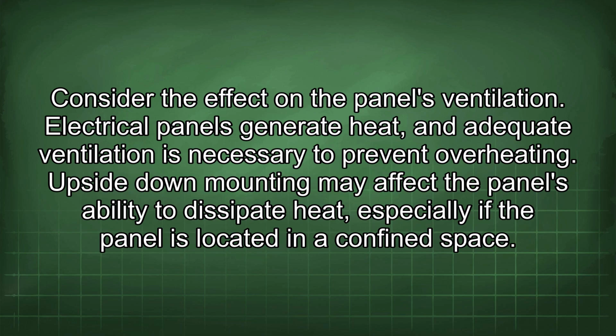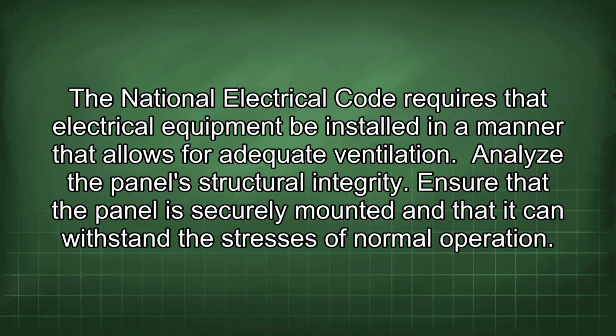Consider the effect on the panel's ventilation. Electrical panels generate heat, and adequate ventilation is necessary to prevent overheating. Upside-down mounting may affect the panel's ability to dissipate heat, especially if the panel is located in a confined space. The National Electrical Code requires that electrical equipment be installed in a manner that allows for adequate ventilation.